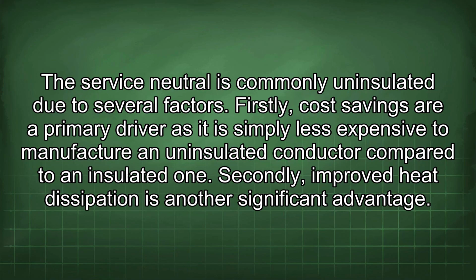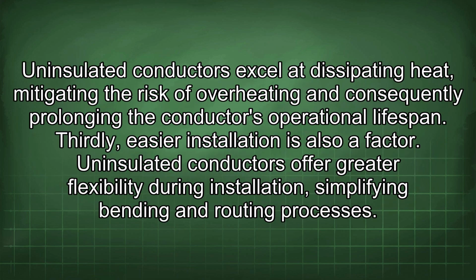Service neutral is commonly uninsulated due to several factors. Firstly, cost savings are a primary driver, as it is simply less expensive to manufacture an uninsulated conductor compared to an insulated one. Secondly, improved heat dissipation is another significant advantage. Uninsulated conductors excel at dissipating heat, mitigating the risk of overheating and consequently prolonging the conductor's operational lifespan.